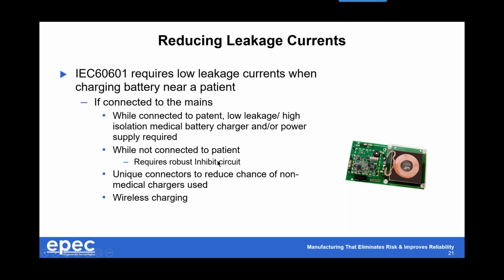If it's not connected to a patient, one of our products, an IV fluid warmer which is also a blood infusion warmer, is designed not to be operated when it's plugged into the wall. So we put in inhibit circuits. If you try plugging it into the wall, it will disconnect the output to the patient, and it will not power whatsoever the medical device attached to the battery. We also went one step further, where you cannot inject any charge current into the output, because a lot of engineers overlook that. They take care of the input, but then some kid on a high school project wants to inject current in through the output, so we inhibit that as well. It becomes fully isolated, accepting no in or out power energy whatsoever, and that's how we design our products. We go a little bit beyond what's normally required, because regulatory agencies never look at the output; they only look at the input.